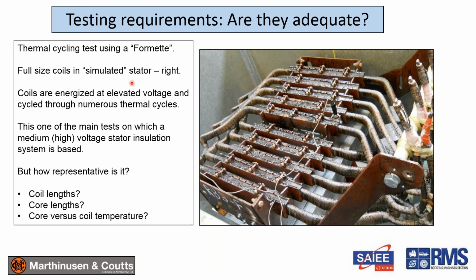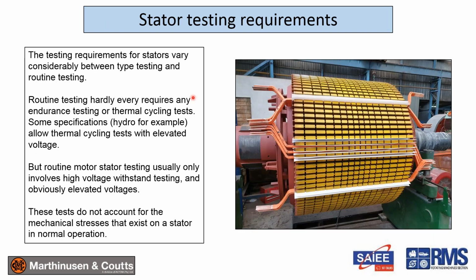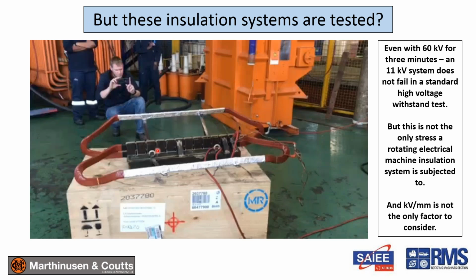And after a while, I looked at the way the testing is done. I think a lot of you know it. It's using a Formette, so it's a simulated stator. So you've got coils, as you see here on your right. The overhang is usually the full size, but the core is often a shorter version of the coil. The example here in our video is actually a Formette, but it's a full size Formette. So we actually replicated the full stator core length.